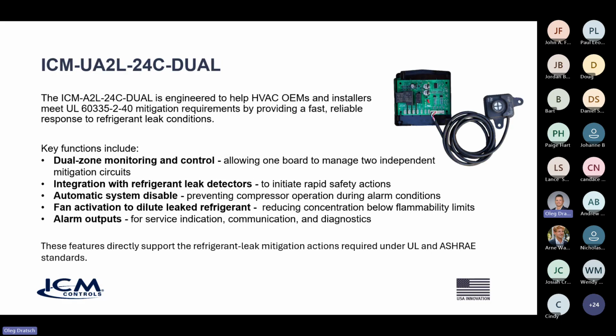So with that, what does ICM Controls have today? So we have a kit, and it's our universal A2L mitigation board paired with the top sensor in the marketplace. And so really what this does, it's able to accomplish dual zone monitoring and control. So it's really monitoring the 24-volt side of the system, it being the thermostat. And it's able to integrate safely in current systems.